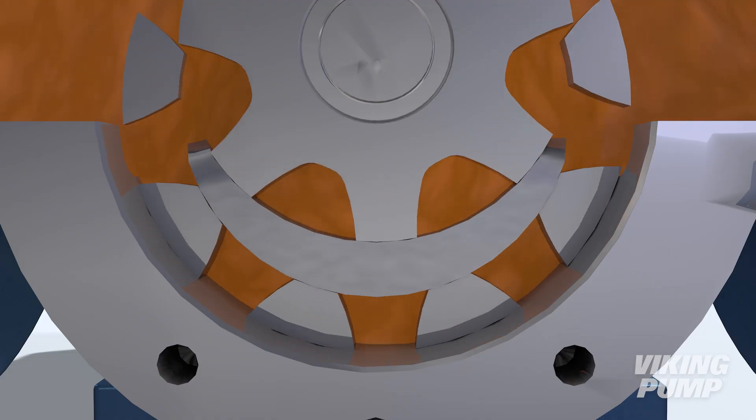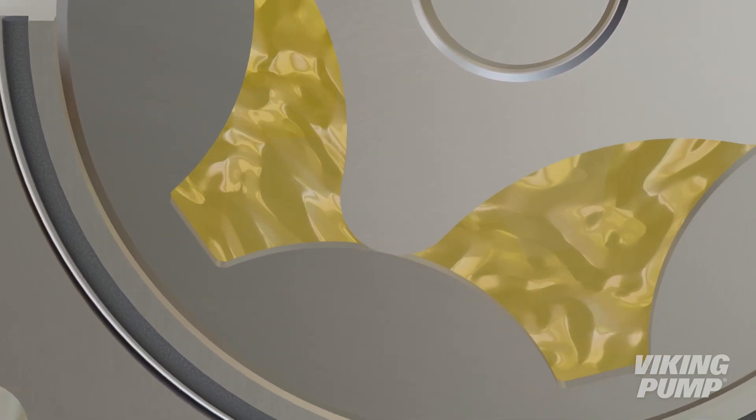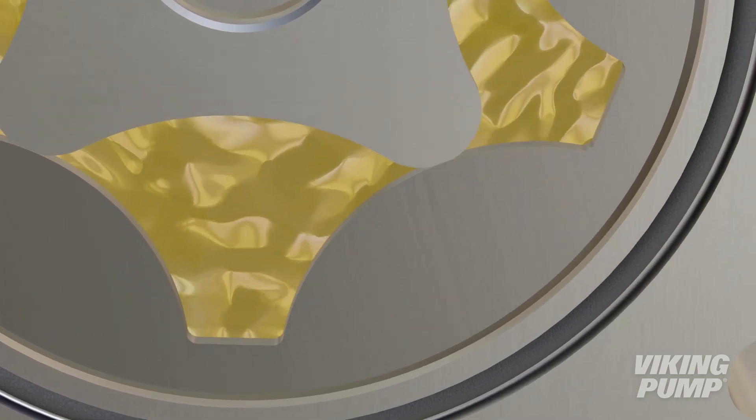A traditional internal gear pump uses the crescent to define the pumping cavities between the teeth of the rotor and the teeth of the idler. In a gerotor pump, the rounded shape of the inner element tooth runs in close clearance to the outer element, creating pumping cavities without the need for a crescent.